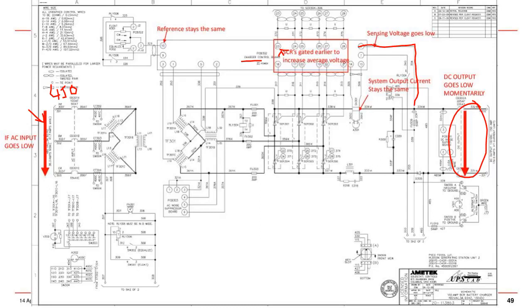Now remember, at no point has the reference voltage changed - we set that through the screen or through the potentiometer, and that doesn't change. Only the sensing voltage changes, and it says it needs to get back to where it needs to be to make sure we have 135 volts on the output.